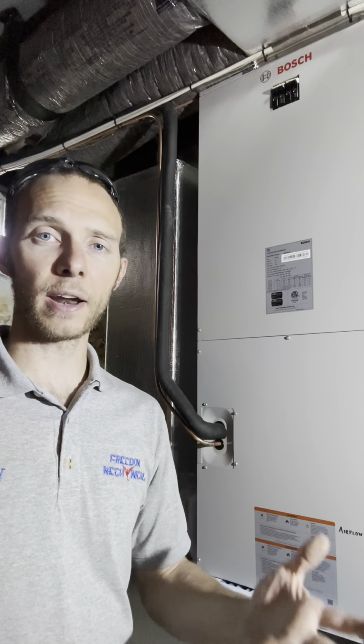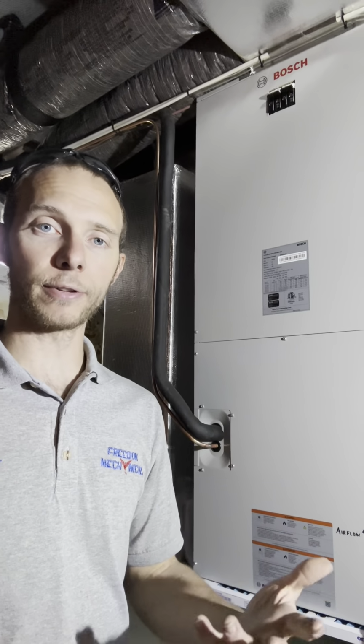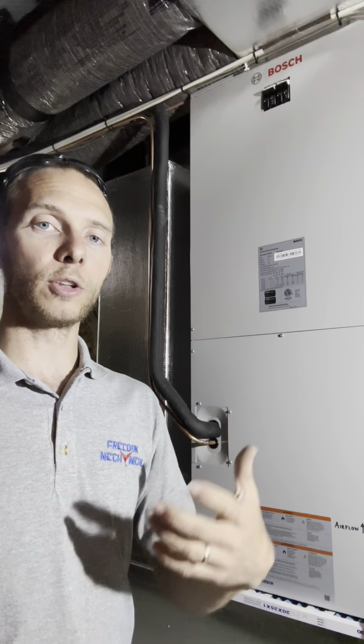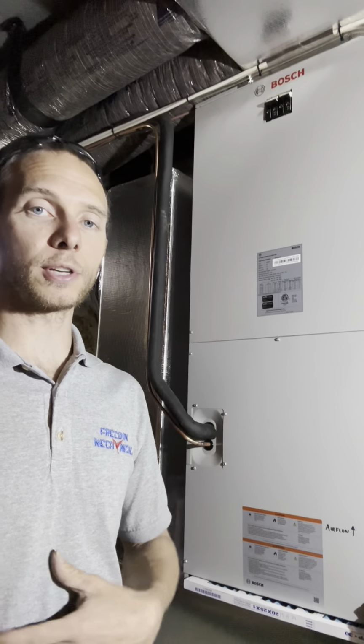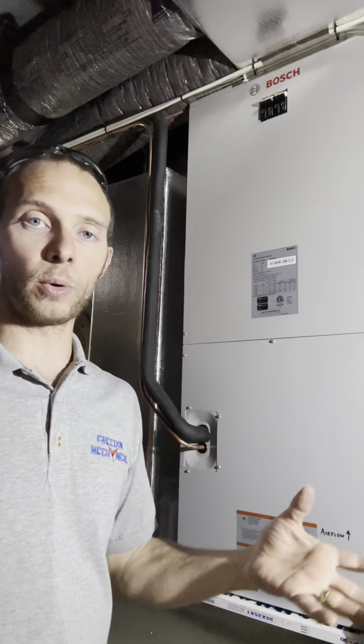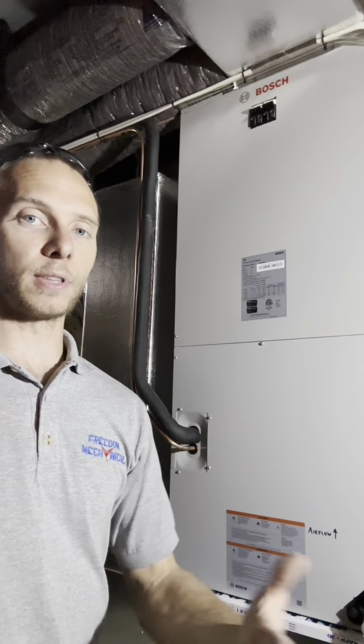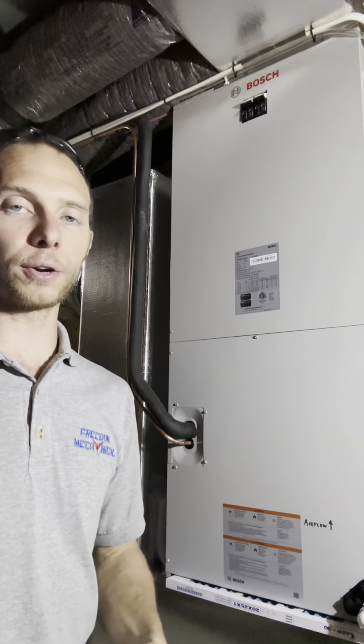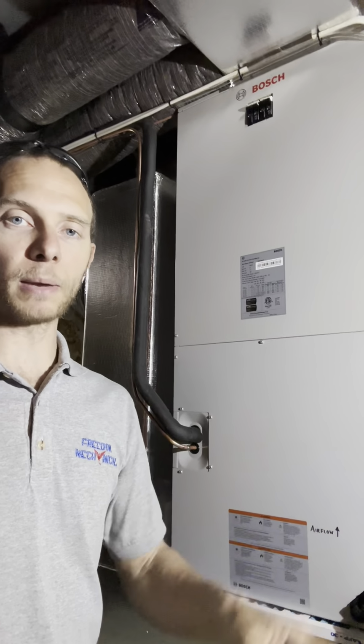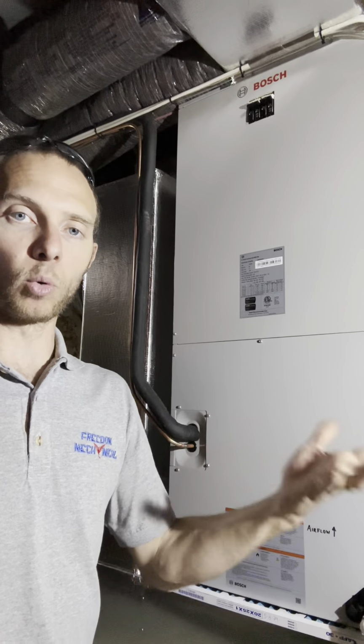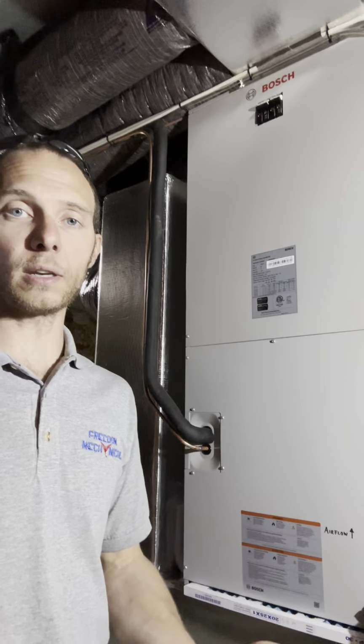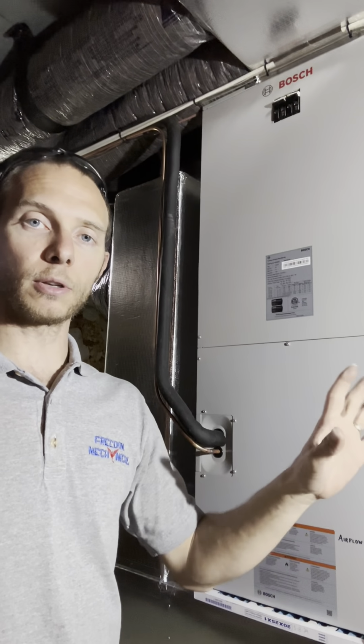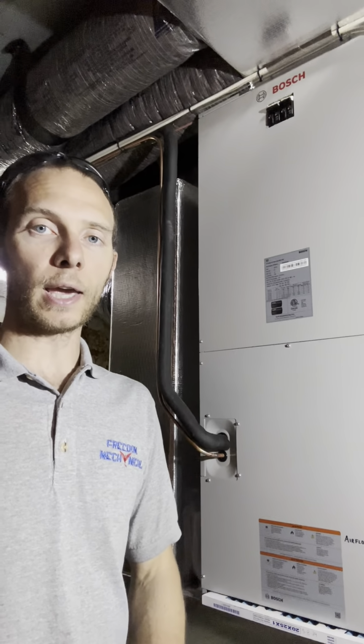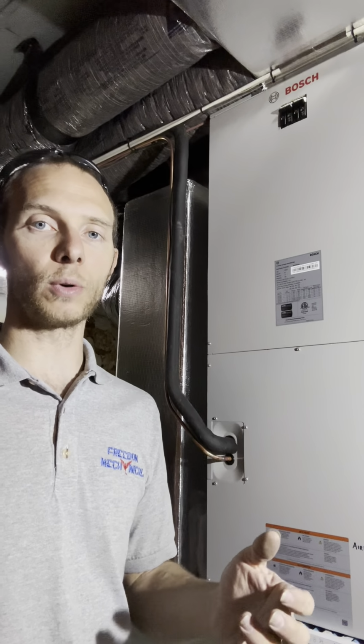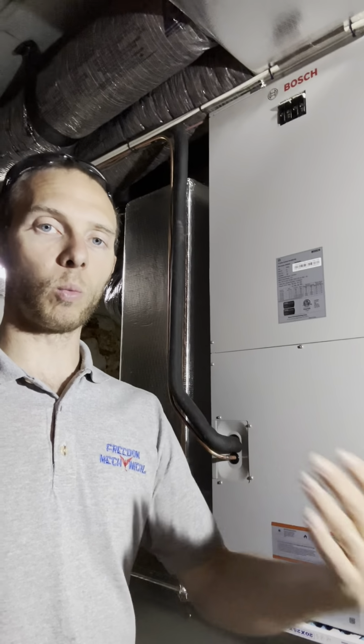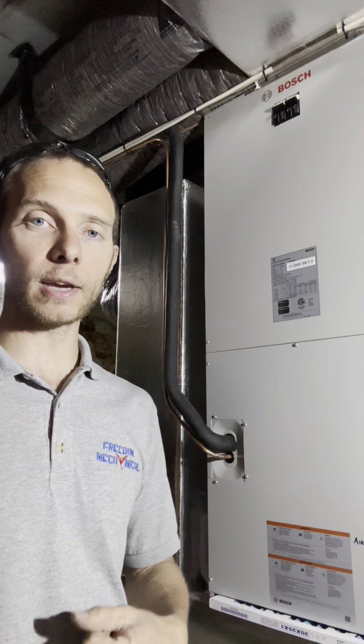Up at the thermostat, I mentioned a delay for the heat to come on. So not everybody has that on their system. This is a Bosch 2.0 air handler. It's nothing that just hit the market or anything like that. They've changed some names for it, but it is a more efficient variable speed air handler. And so it has a little bit of a smart computer to it. And what that allows it to do is control when the fan comes on for heat.